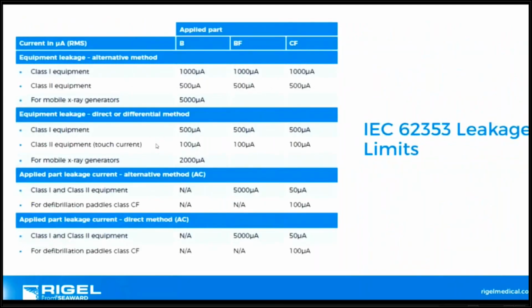We have some different pass/fail thresholds for the classifications with class 1 and class 2. We've got alternative methods. We've got the direct and differential. Again, all of these, it's nice to have a familiarity or some understanding to be informed in pass/fail thresholds as far as the standards are concerned. But most safety analyzers will do this automatically and bring to the attention that you do have a failure.